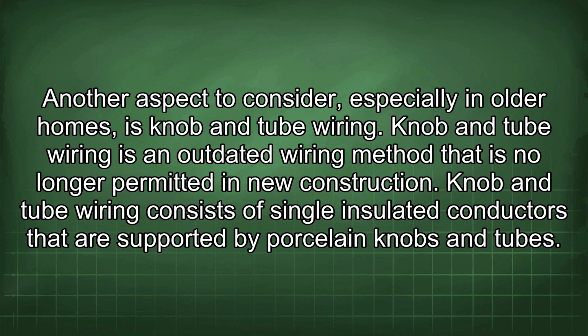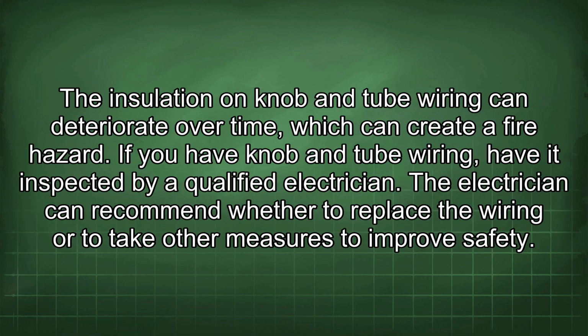Knob and tube wiring consists of single insulated conductors that are supported by porcelain knobs and tubes. The insulation on knob and tube wiring can deteriorate over time, which can create a fire hazard. If you have knob and tube wiring, have it inspected by a qualified electrician. The electrician can recommend whether to replace the wiring or to take other measures to improve safety.